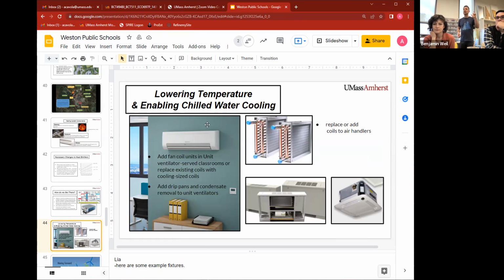At the field school, you have rooftop units serving the classrooms with DX cooling right now, meaning cooling via heat exchange with the air and direct gas-fired heating. Those units wouldn't integrate with the system at all for now, and until you felt the need to replace them, they'd operate just as they always have, with their own heating and cooling not tied into the system. Over time, you could replace those rooftop units with ones that do integrate directly with the system, likely ones with heat pumps built in, using the water from the thermal loop of the whole energy system directly rather than a circulating loop.